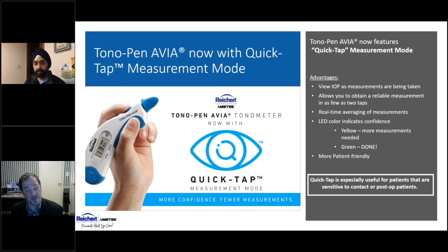So if you really just need a quick and dirty, you will get a number with one tap of the cornea. But the LED on the device now will change colors depending on the reliability of the measurement based on the standard deviation of the data it's obtaining. So you can get a green light, which means high confidence reading, in as few as 2 taps if you get good, clean, quality IOP data from a proper tap of the cornea.